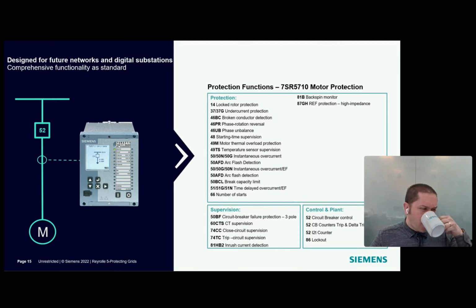Now, 14, locked rotor protection, for example, uses different time overcurrent elements to monitor motor start conditions. Or 48, starting time supervision. This allows the motor starting time to be monitored and output is raised if the start time exceeds the setting.